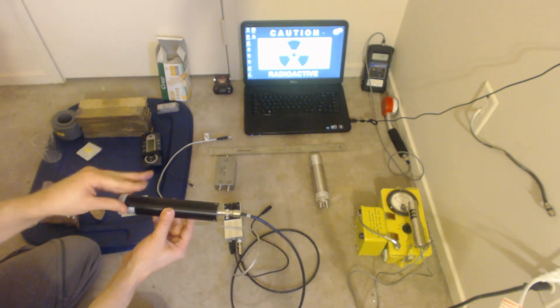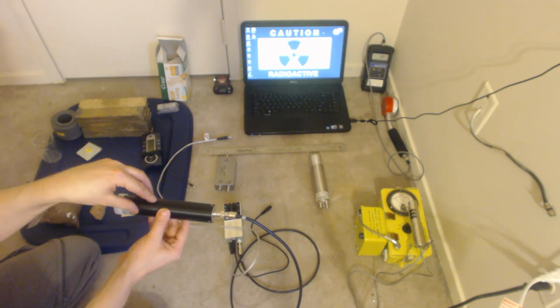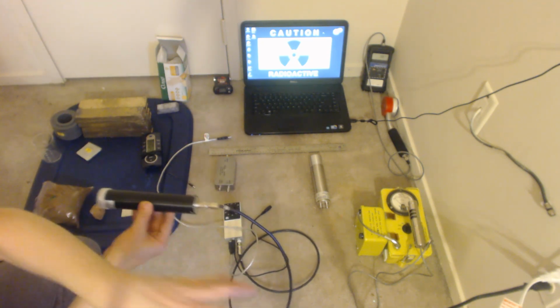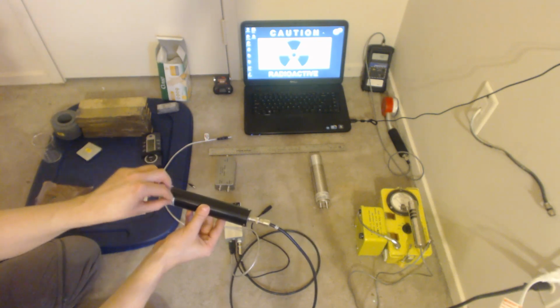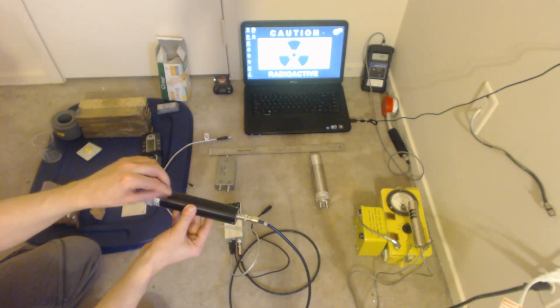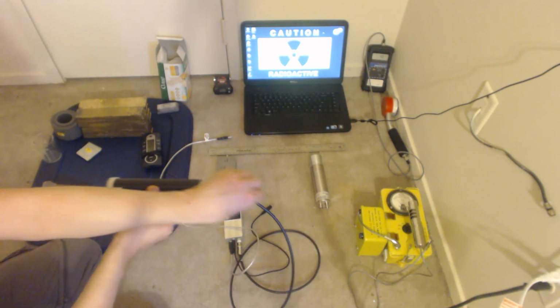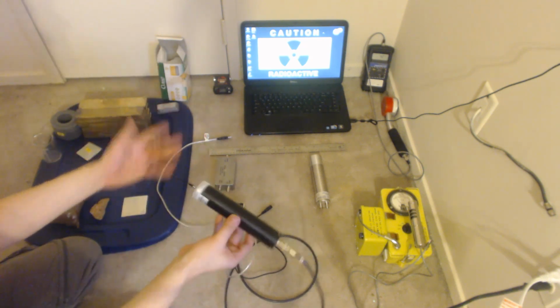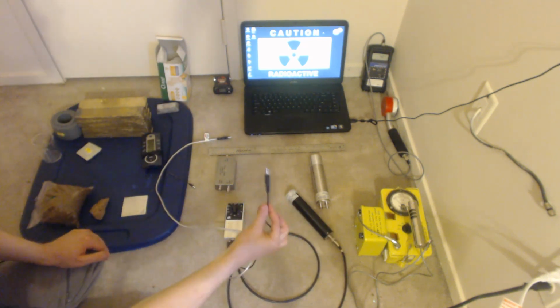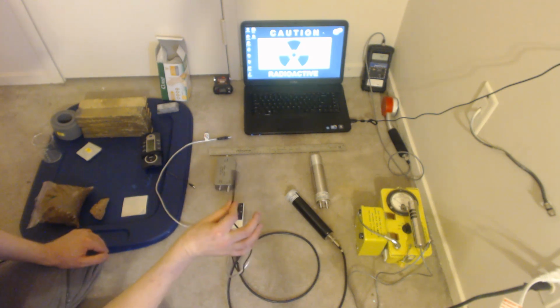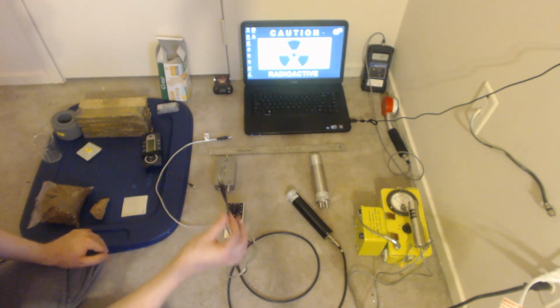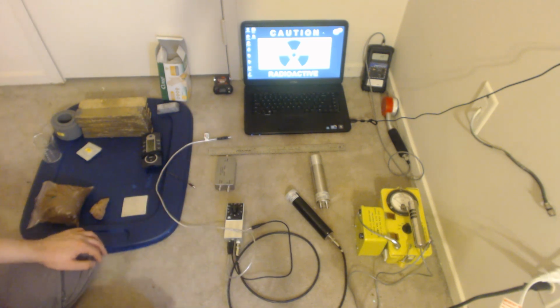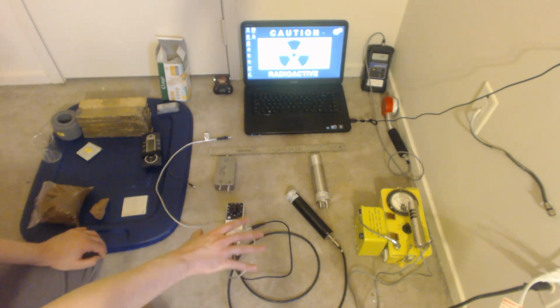High energy gamma, lots of photons, more electrons, becomes a stronger pulse. Low energy gamma, not so many photons, only a couple electrons, still builds up, but the resulting pulse is less. Proportionate. The resulting sound output is proportionate too. High energy gamma, big volume. Low energy gamma, little volume. And that is the basics of how the unit is capable of determining energy.